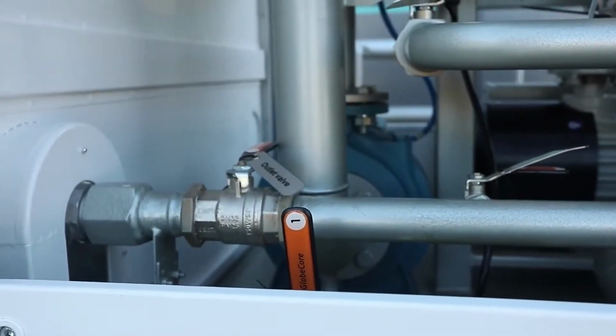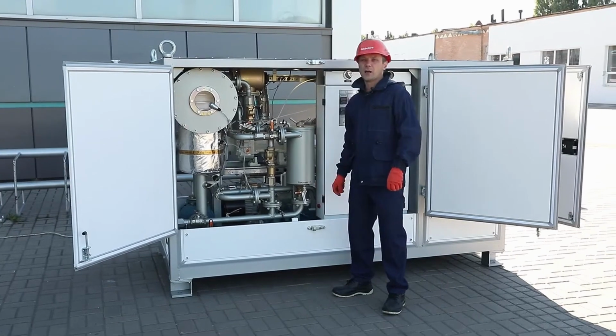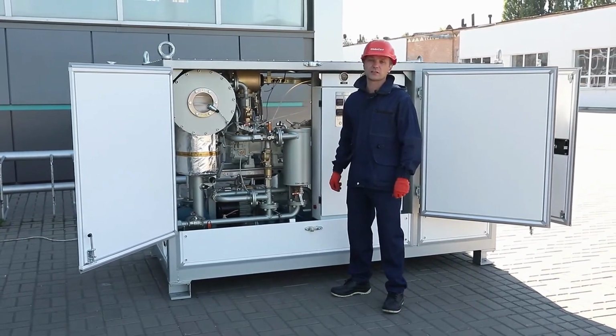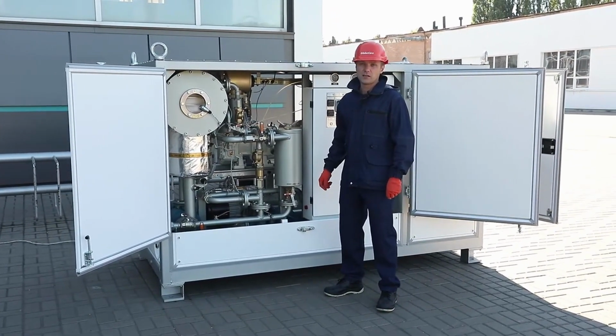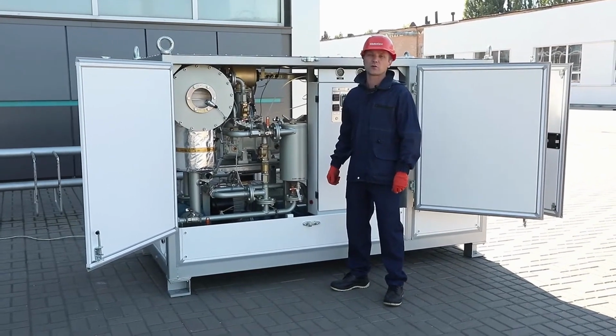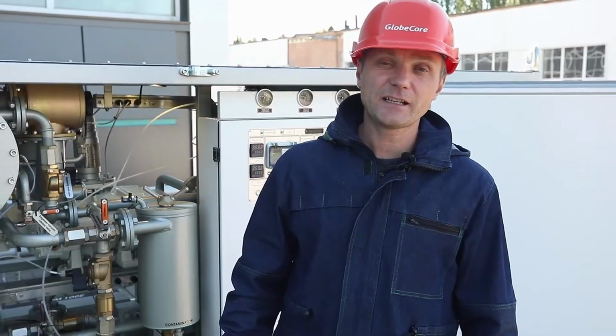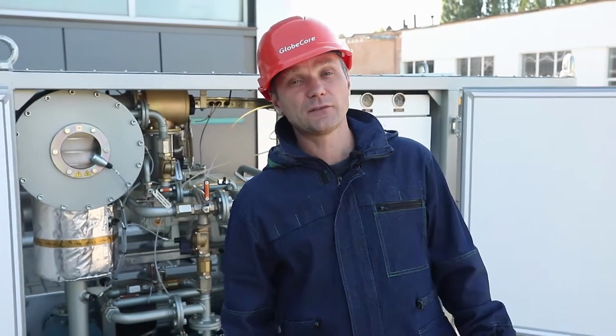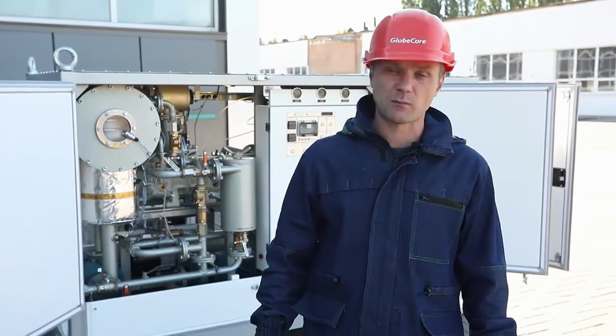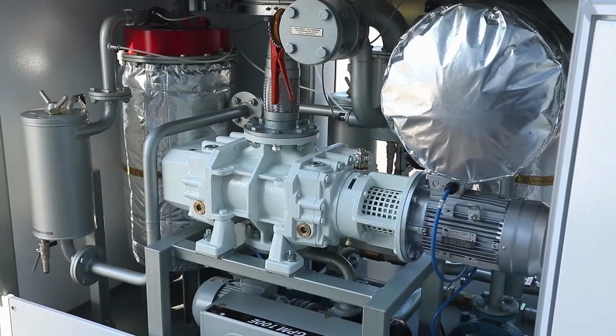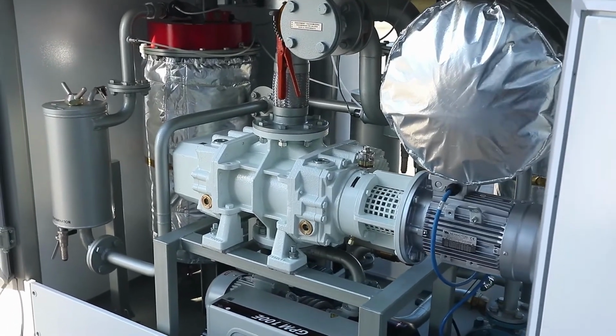Some components of the unit can be used offline and operate in other modes for implementation of process steps in maintenance of transformers. A tape heater is engaged when flushing the transformers with hot insulating oil, and a vacuum system operates during transformer vacuumizing. In degassing, drying, and filtration modes, the capacity of the unit is 6 cubic meters per hour.